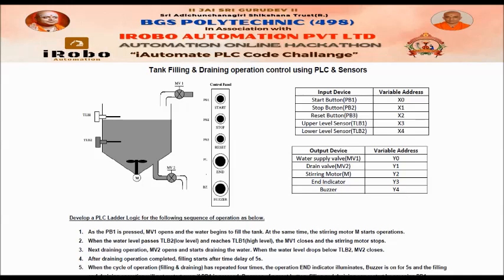When filling is completed, the next draining operation starts: MV2 opens and begins draining the water. When the water level drops below TLB2, MV2 closes — meaning draining stops. When MV2 closes and draining is completed, there is a delay of 5 seconds before filling starts again, repeating from step 1 to step 3.